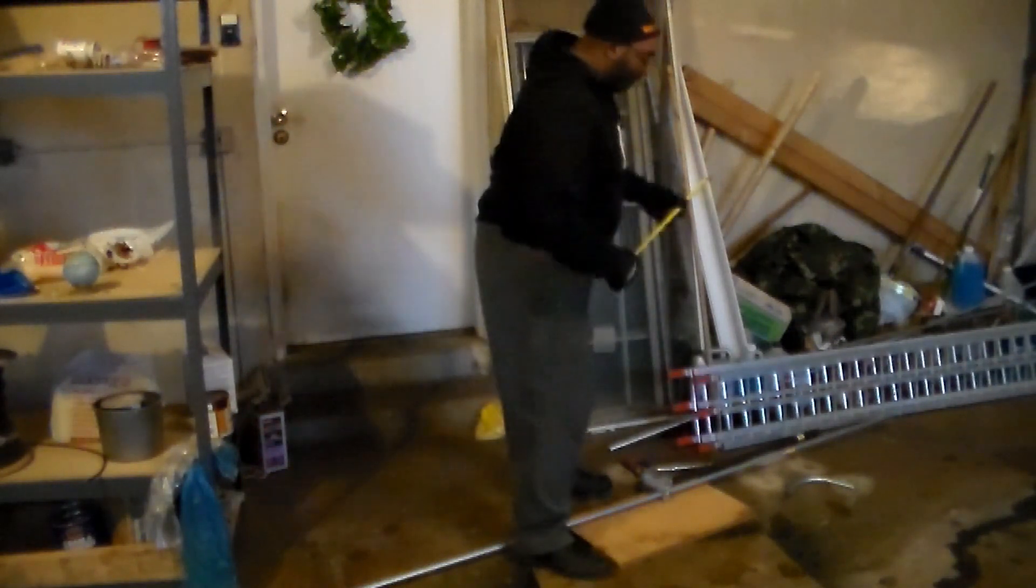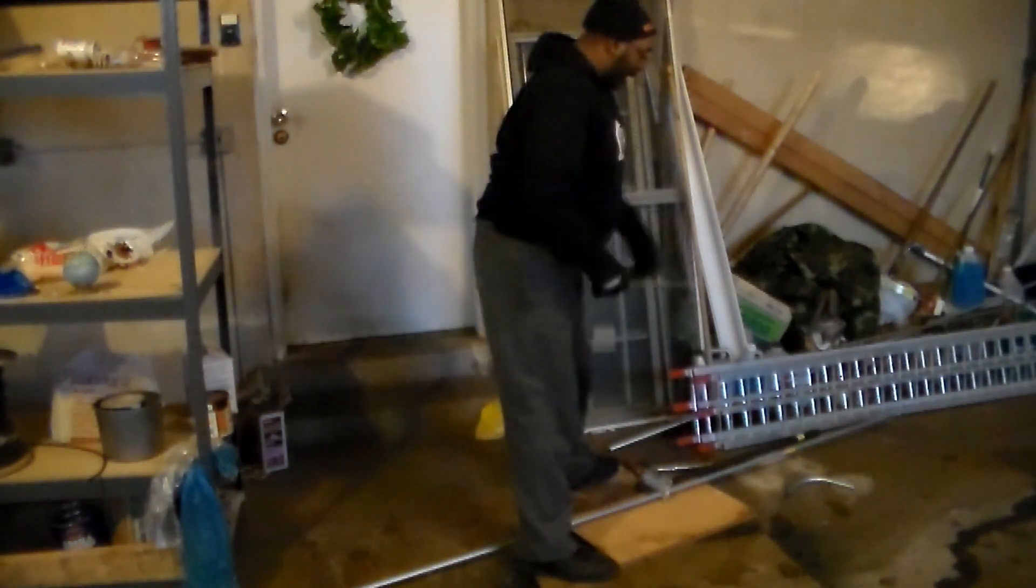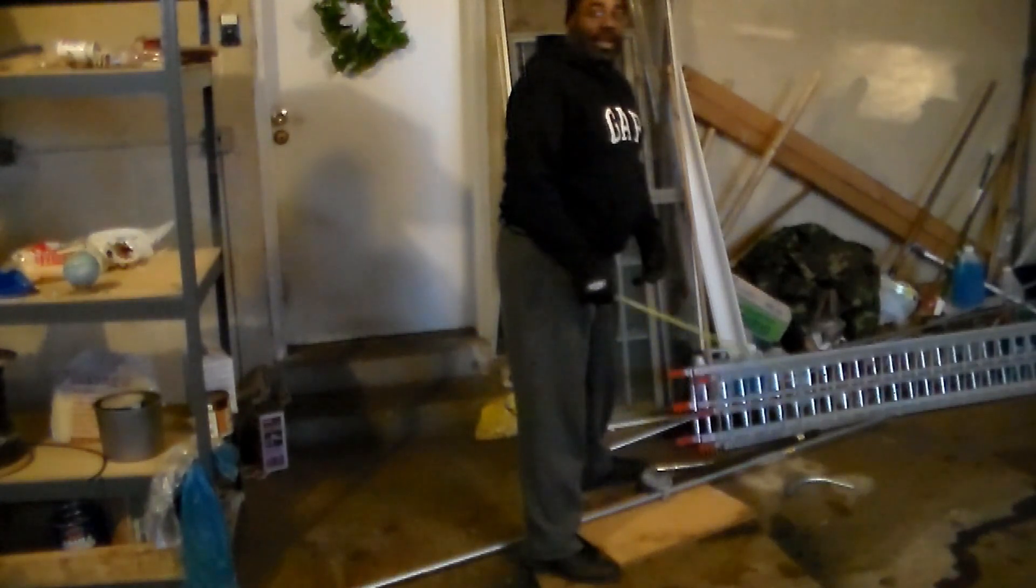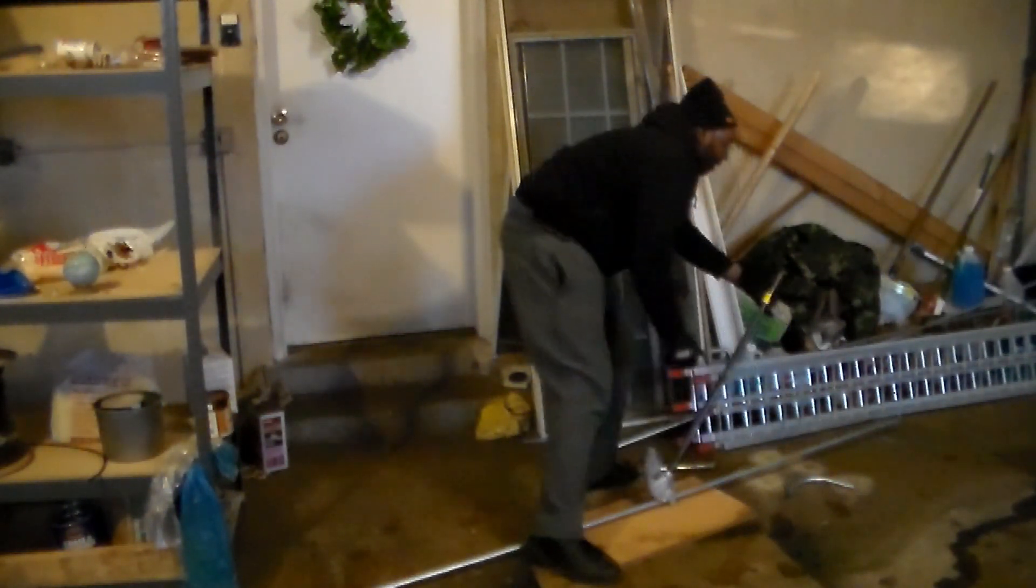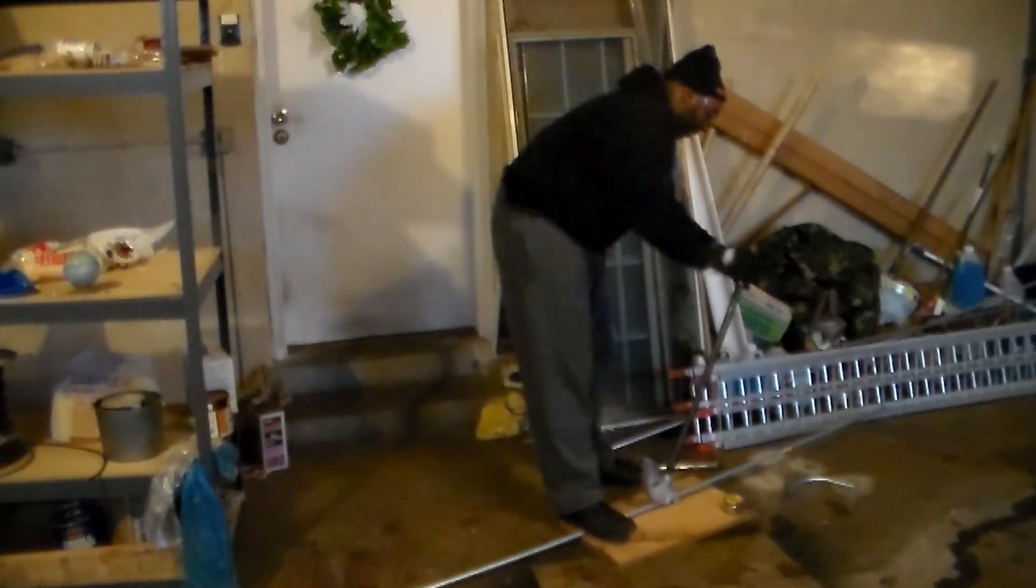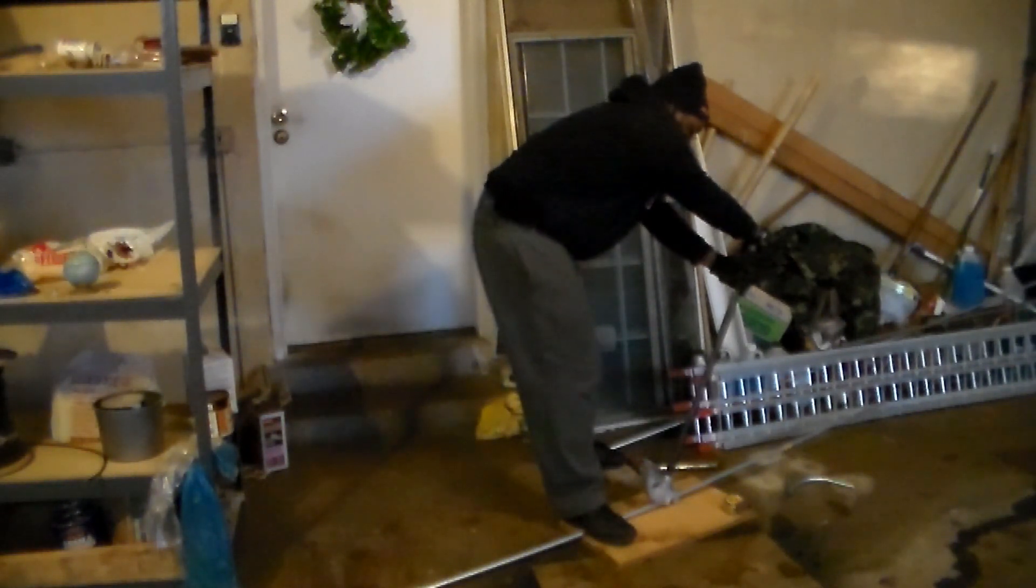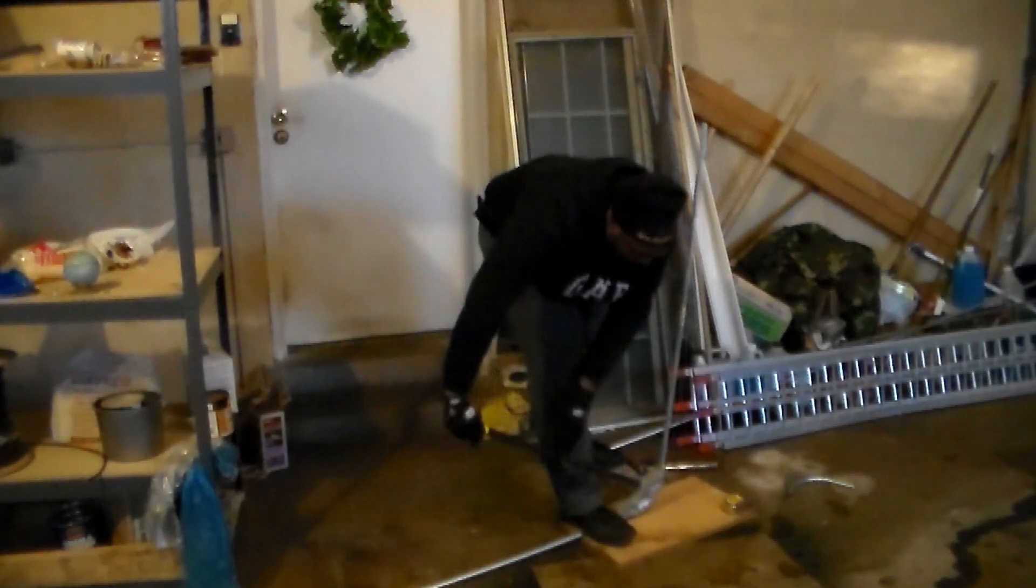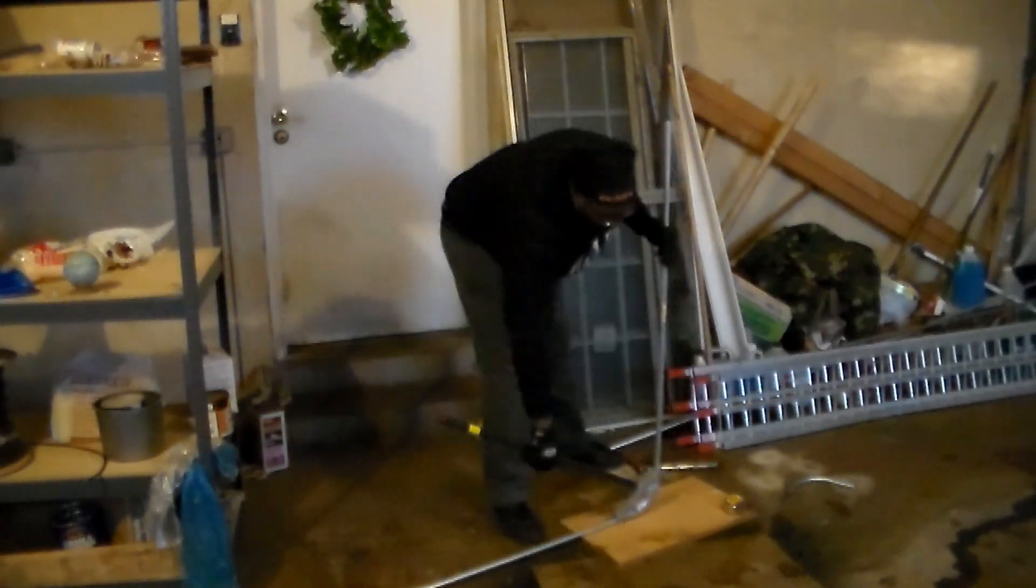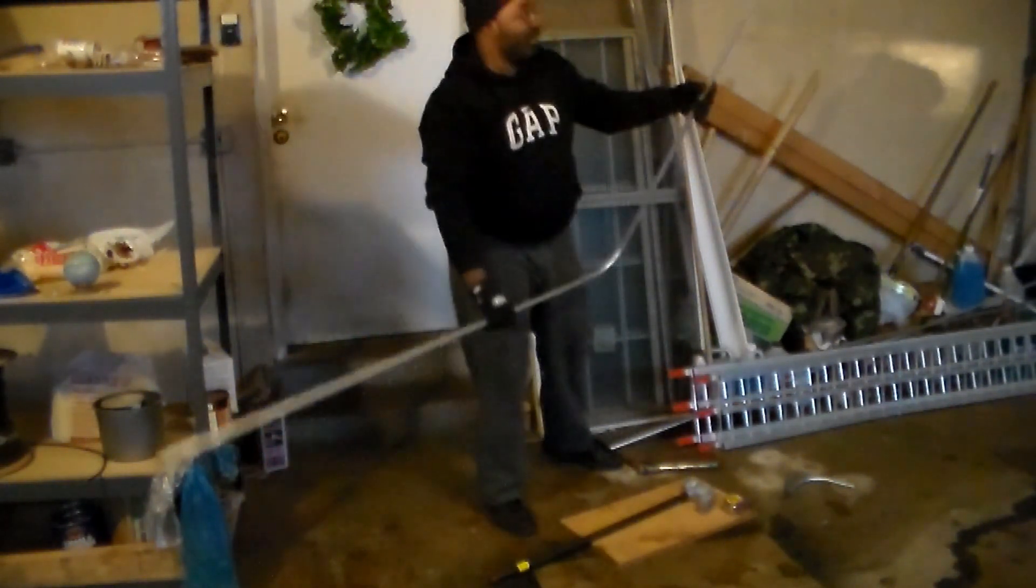Now because of the fact that I need to bend to a curve at 48 inches from the box going up, and this bender has a 2½ inch gain, so 48 minus 2½ is 45½. So that's where I'm going to start bending at 45½. And when bending conduit, use an even amount of pressure, steady pressure through the whole bend so you don't get a kink in it.